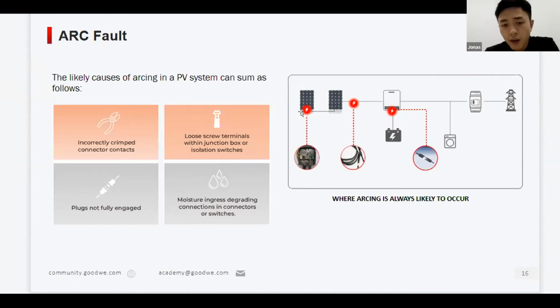The parts most likely to cause an arc fault are the connectors and damaged cables. Also, in a battery, between the connection of the battery and the inverter, there could be an arc fault. And we all know recently there are some news reports about battery ignition. So it is very important to identify the arc fault on these parts.